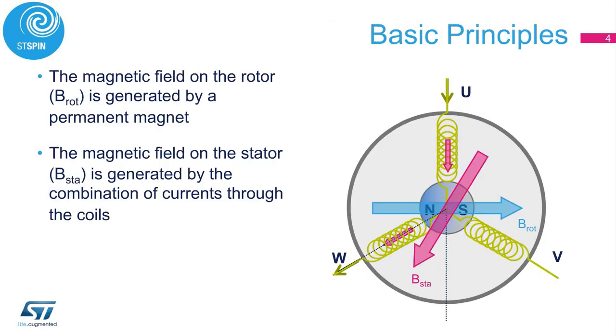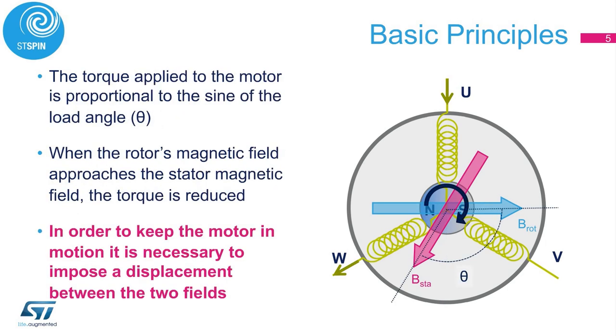The rotor magnetic field is always present and is generated by a permanent magnet. When a current flows from one motor phase to another, the magnetic fields are combined and generate the stator field. By applying the right voltage at the right time to the motor phases, we obtain currents which generate a rotating magnetic field. The magnetic field is directly proportional to the current through the coil or winding. The output torque of an electrical motor depends on the intensity of the rotor and stator magnetic fields and on their phase relation. The angle between those two magnetic vectors is called a load angle, theta.